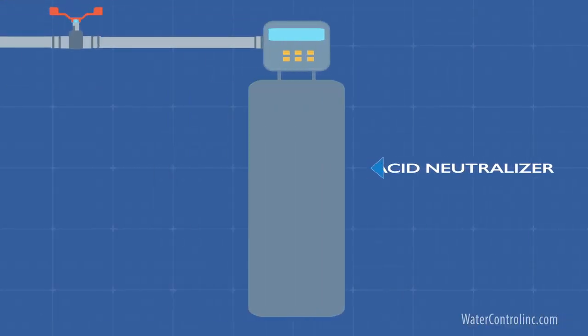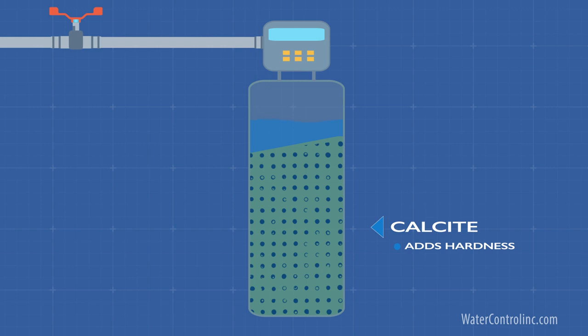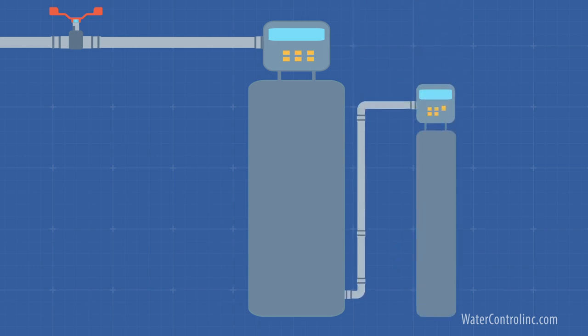Acidic water is relatively easy to deal with. Typically, the water is run through a filter that looks like a water softener, but without any salt tank. The media in that tank is calcite — basically, it's limestone. It adds a small amount of hardness to the solution, to the tune of about four to six grains, and it neutralizes the acid in the process. If this low-level hardness is problematic for your application, a water softener can be installed downstream.